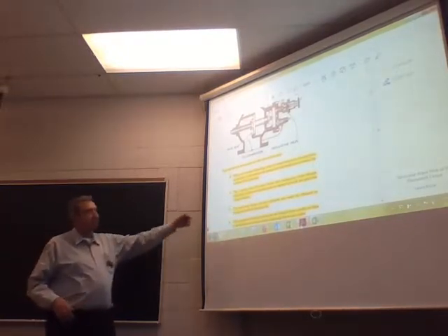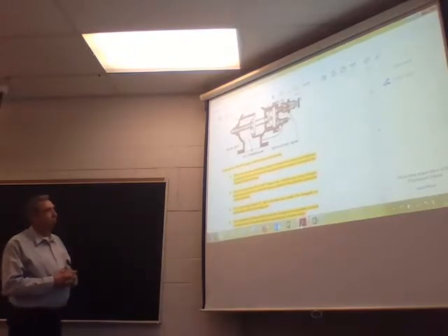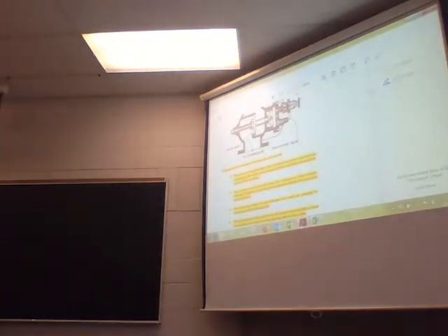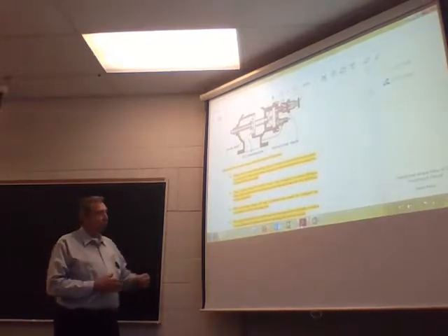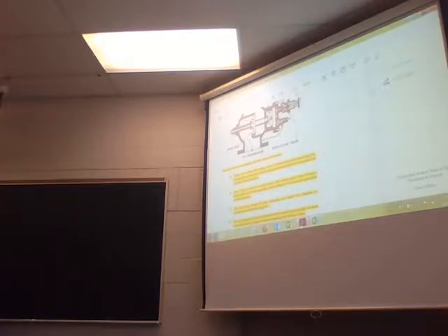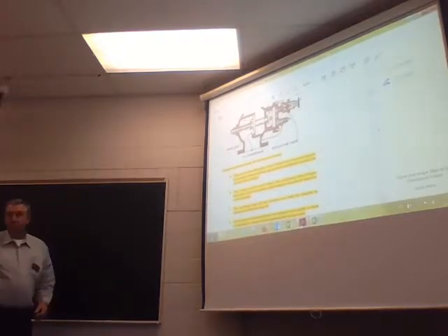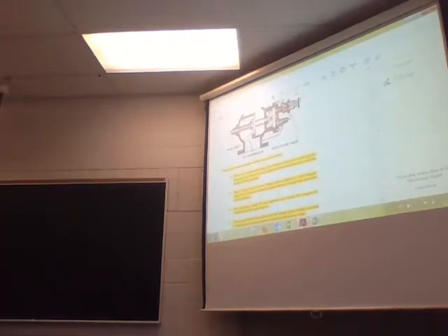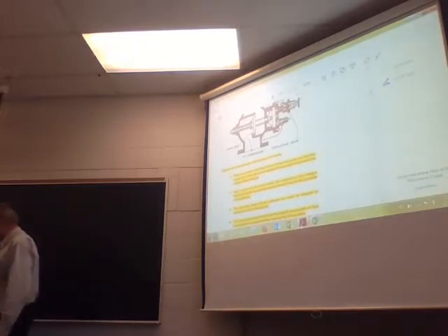Same idea as our unloader. This system can be used where the compressor load changes frequently, as the air receiver pressure directly controls it. So if we want to change the pressure in our tank, you can see up there we've got an adjustment. We can actually change that to overcome that. The operating range can be easily changed or adjusted by the adjustment nut.